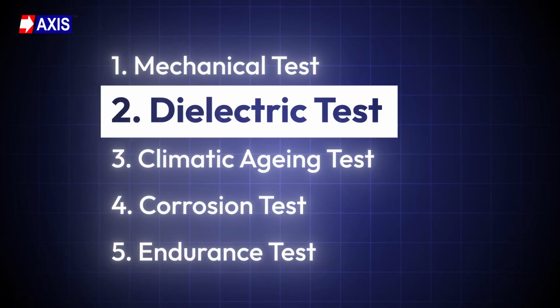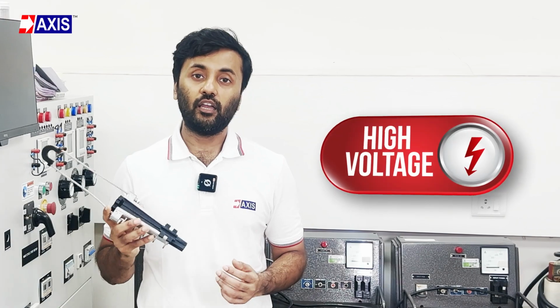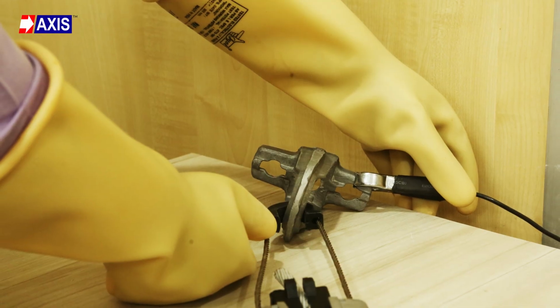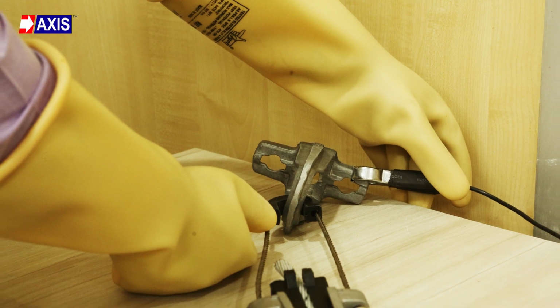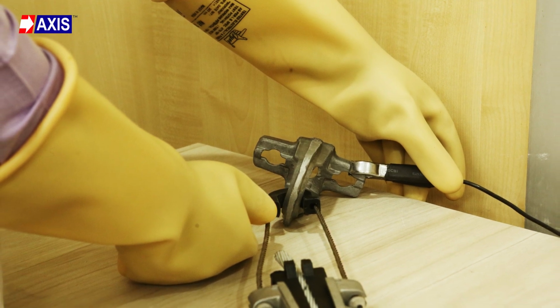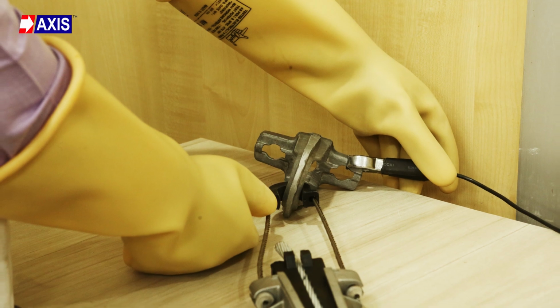Secondly, the dielectric test. The purpose of this test is to check if your tension clamp can maintain insulation and resist electrical breakdown under high voltage. To perform this test, mount the tension clamp on an uninsulated conductor. The conductor must stick out at least 5 cm from each end of the clamp. Cap the ends of the conductor to avoid flashover. Earth all exposed conductive parts. Connect the high voltage source between the conductor and the conductive part of the clamp.